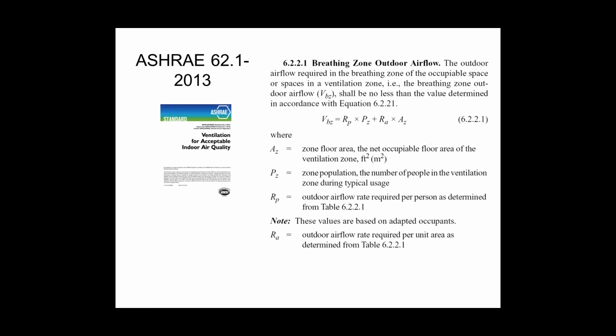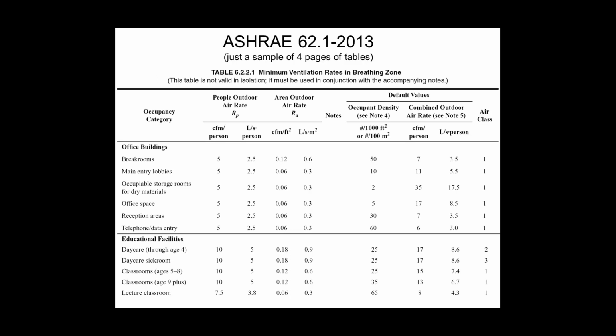So from a controls perspective, what you really need to know is that it's a per person plus a per square foot number that equals the total. The controls designer is probably not the one doing this, right? The mechanical designer is, and they're just giving you the number saying, we need this much air for these different air handlers. Where it comes into play for you on the control side as a controls designer is that ASHRAE has separated these into two different numbers, and you can see here I highlighted an office space. It requires 5 CFM per person plus 0.06 CFM per square foot, whereas the old standard, 12 plus years ago, was just 20 CFM per person total.